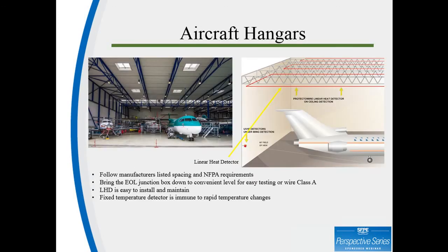Aircraft hangars are another common application for linear heat detection. Given the often varying ceiling heights, you should consult NFPA's reduced spacing chart, which covers up to a 30-foot ceiling height, or NFPA's listed spacing exemption rule, the 0.4 times the ceiling height, but you cannot exceed the maximum listed spacing. Both of these were covered earlier by John today.